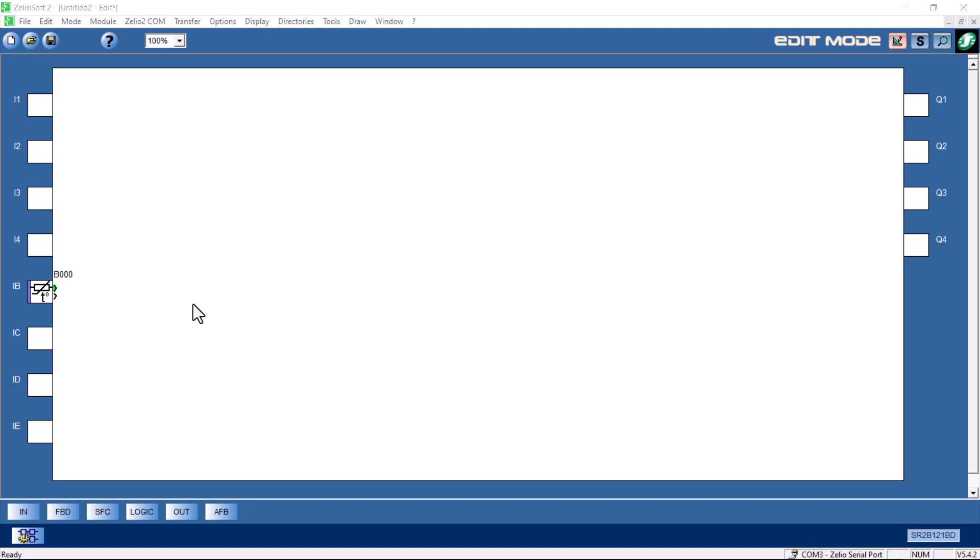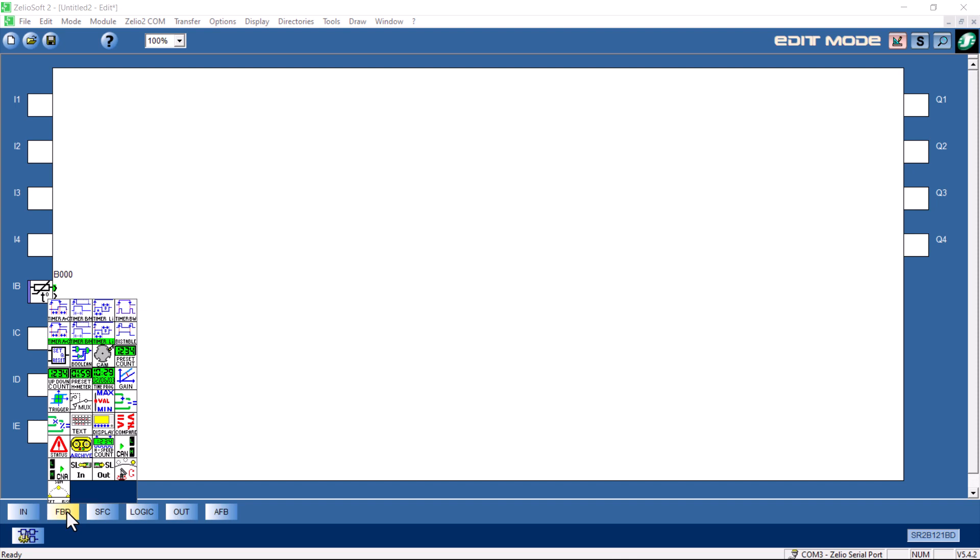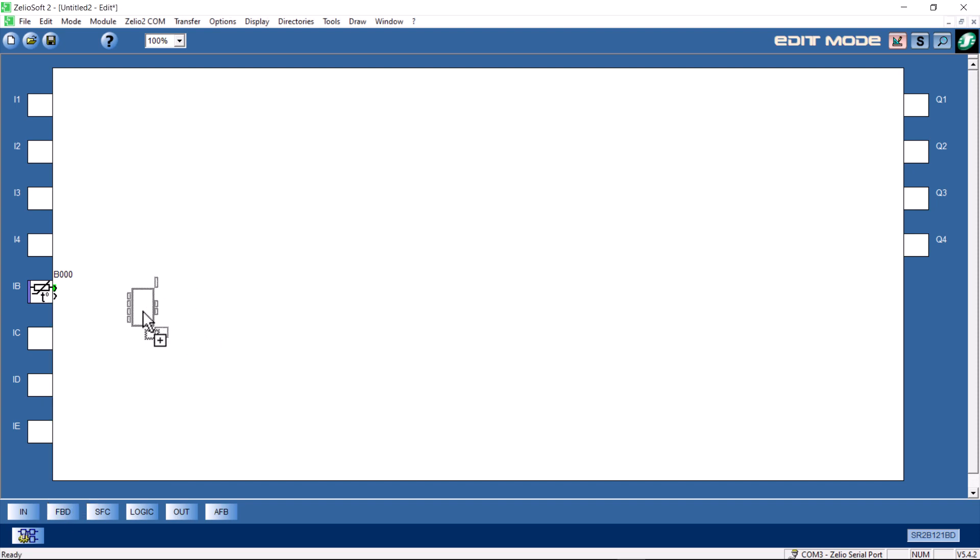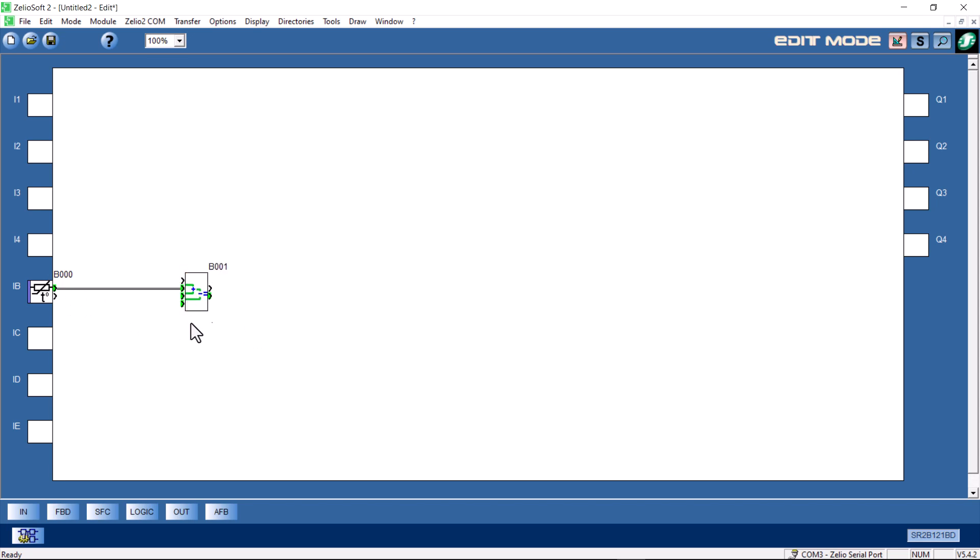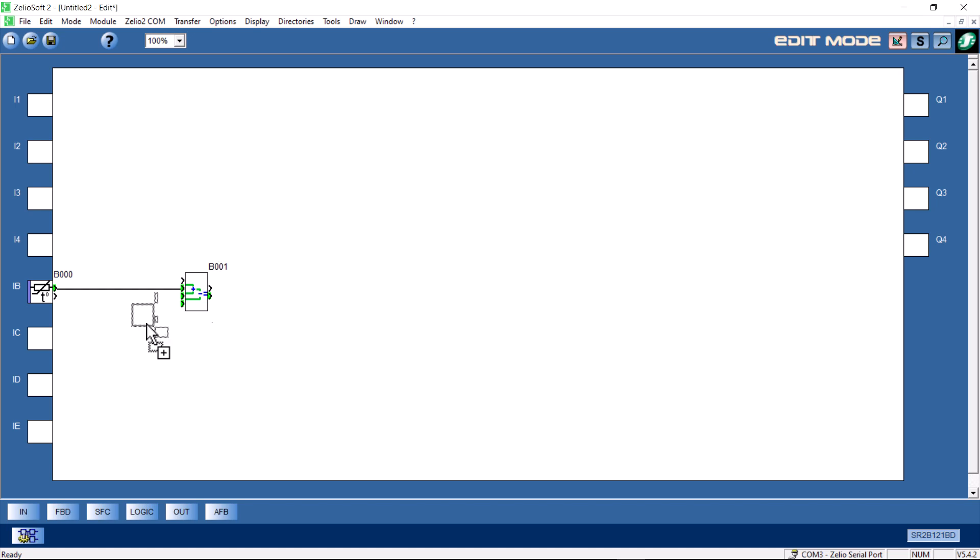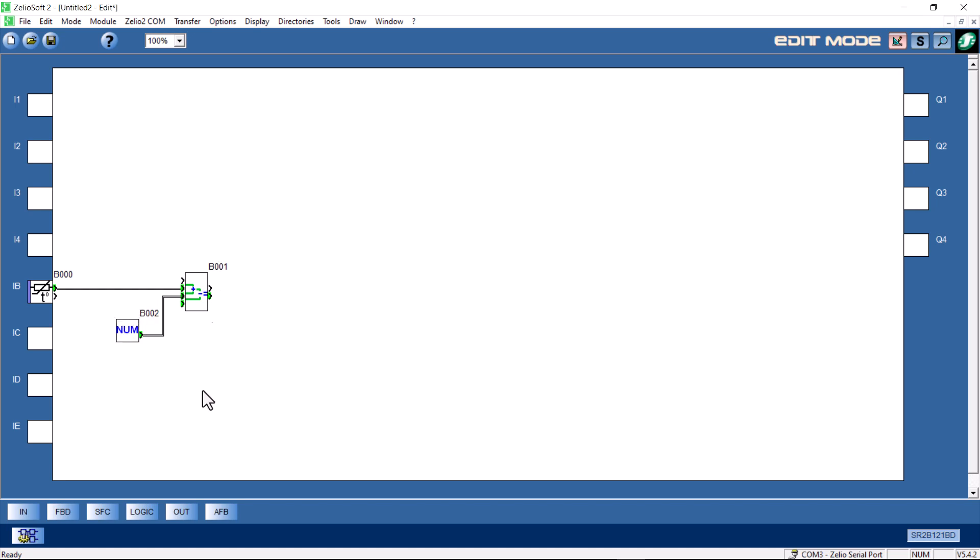The next step is to put the text block in to display that temperature. But first, we need to put a function in to allow us to calibrate the thermistor if it is off. I'll show you how to do that. We'll go down to function block here. Click on function block. I'm going to look for a little math block. Basically, it's just a straight addition block. I'll take that value from the temperature sensor and connect it to one of those inputs on the block. Basically, the input value plus the offset will result in a calculation output.